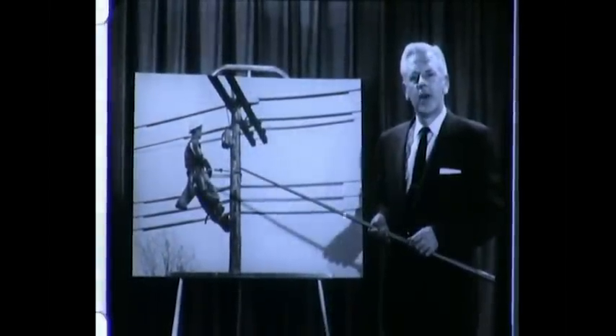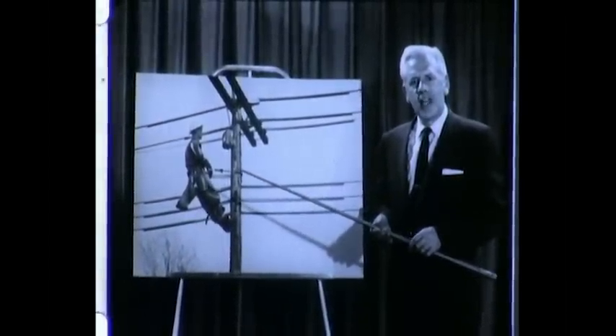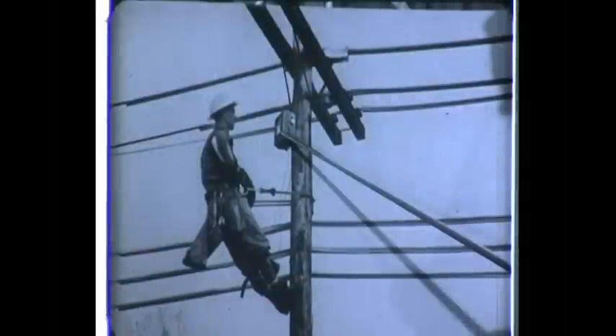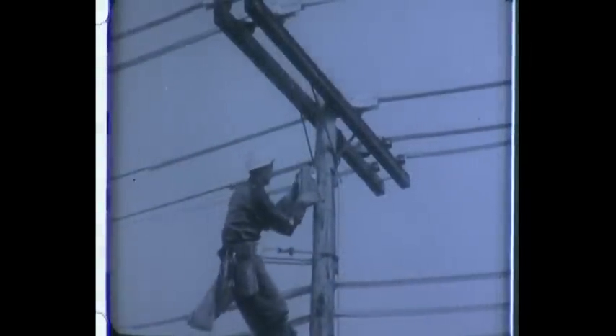From the instrument department comes an easy way to analyze electrical load problems. The CF7 inkless recorder. The CF7 is a lightweight, portable instrument for recording either current or voltage. It's put into action in 4 easy steps without causing any interruption in service. Here's how it's done when measuring current.